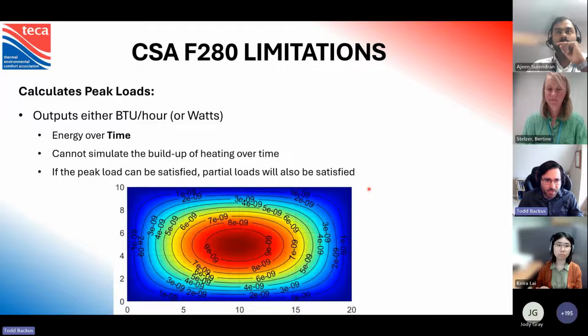One of the limitations of CSA F280 that's actually very important to understand is that this is a peak load calculator. So the output is going to give you either BTUs per hour or watts, depending on if you're imperial or metric, and it's energy over time. So what this cannot do is simulate the buildup of heat in a dwelling over time. And that is a limitation. So this is a peak load calculator. We look at the absolute worst case scenario, and then based off that, we say, well, if we can meet the peak load, partial loads will be fine.